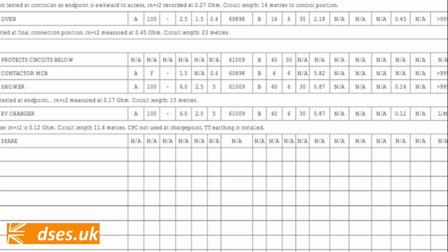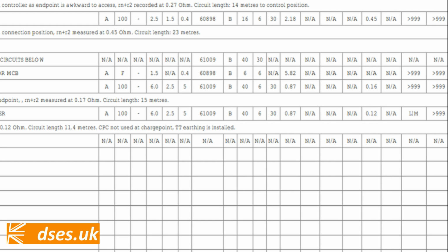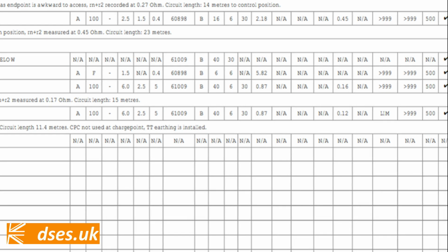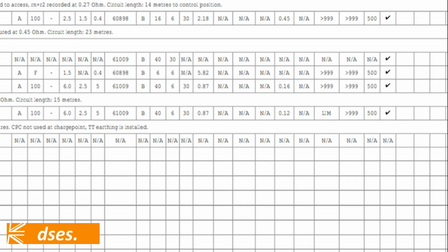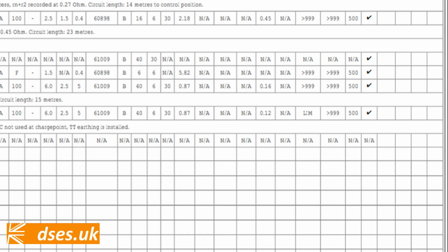And it's a good thing that Rn was checked, as I found poor connections along neutral both on my immersion heater and on one of my underfloor heating supplies, which, being resistive heated loads, would likely have tripped up the AFDDs employed on those circuits at some point.